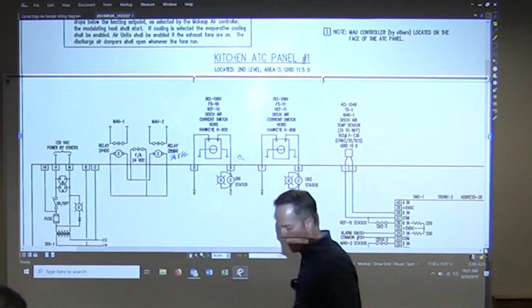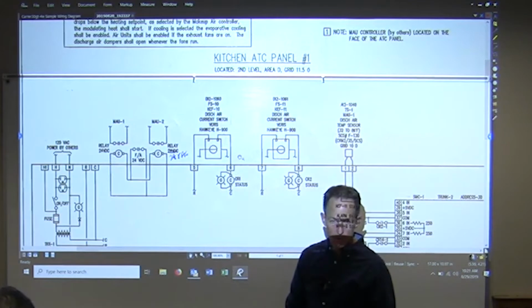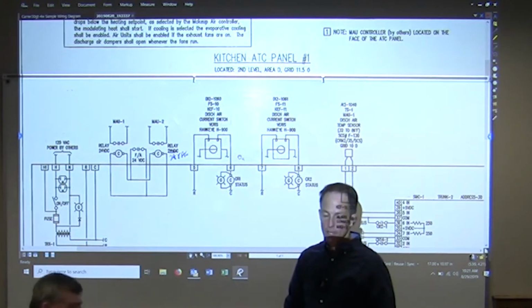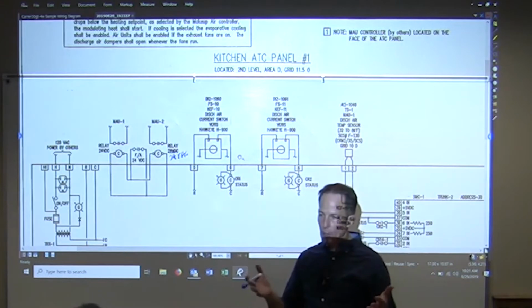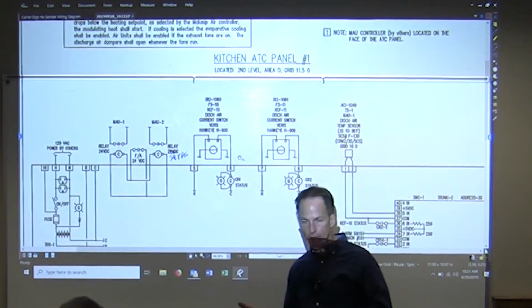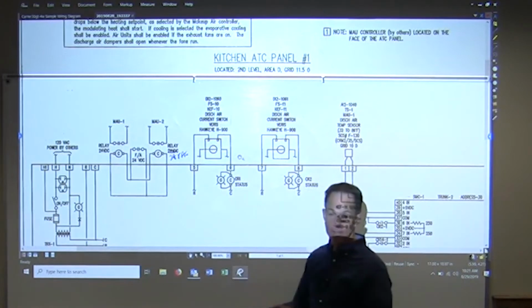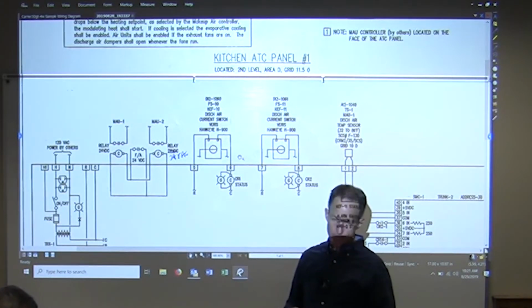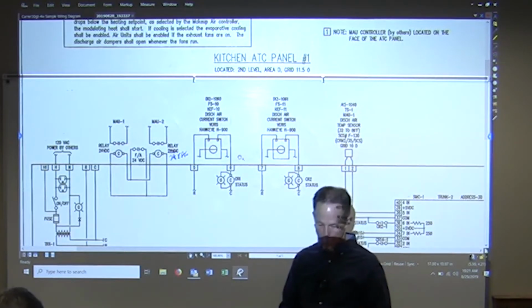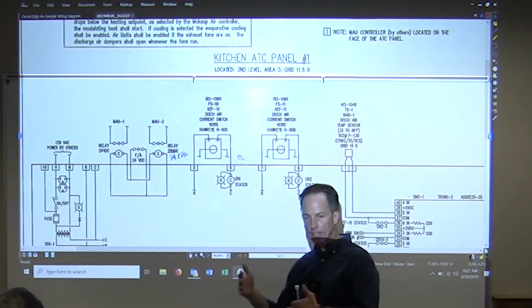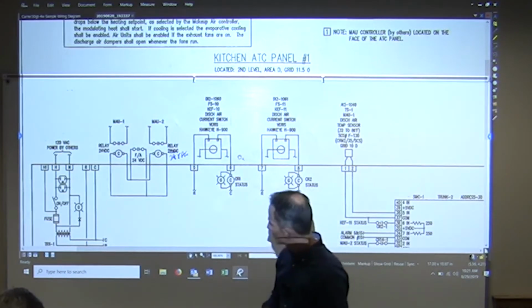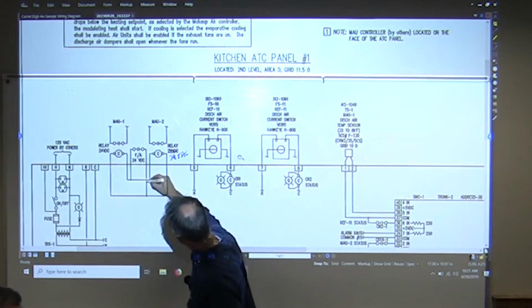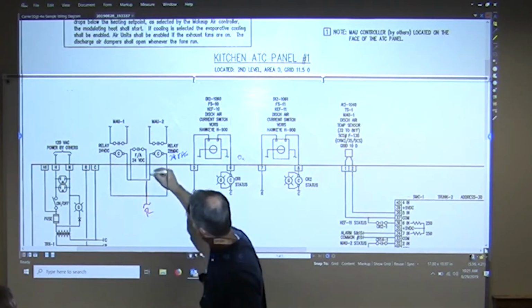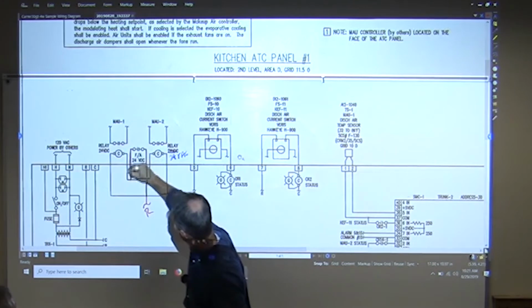Why do we usually want to run our high side through the contact first? So there's not power at the relay all the time. Yeah, it's a best practices kind of thing. Can you switch the common side? It happens. You run a risk of one side of the transformer being grounded, and then if your wire gets grounded, it turns things on. It does. And so you can get some things happen that you don't want. So that's why we try to always switch the high side. So instead of what I originally drew, we're going to bring this down to our R, up through there.